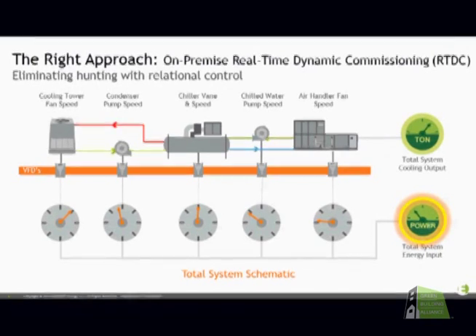If it's only going to drop below whatever your threshold temperature is - say 39 degrees is pretty common - if it's only going to be 38 for an hour and a half, the penalty you're paying is turning on and off all this equipment, because the chiller is large enough that there's inrush current to it. It takes a lot of power to turn on and off, so you don't want to do that. It can also damage equipment if you're regularly turning things on and off.